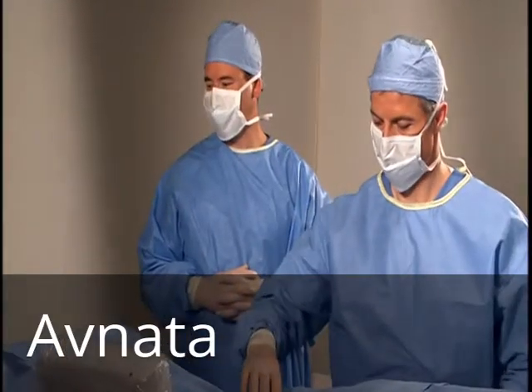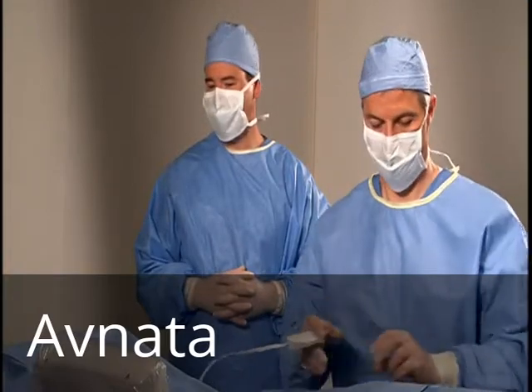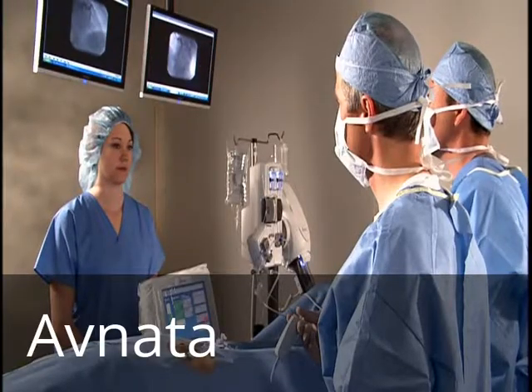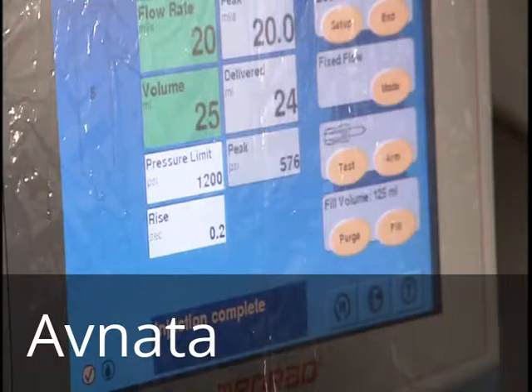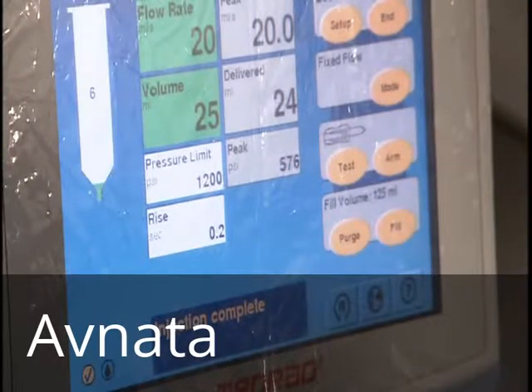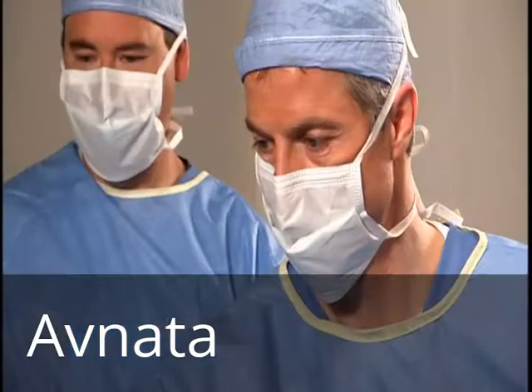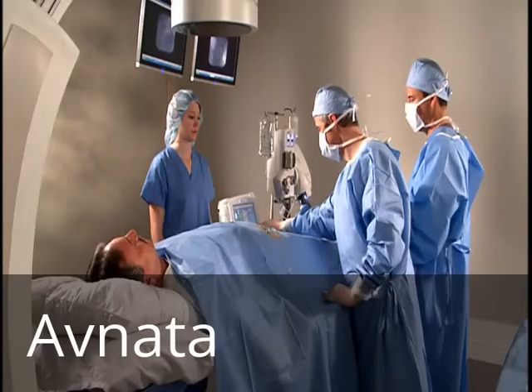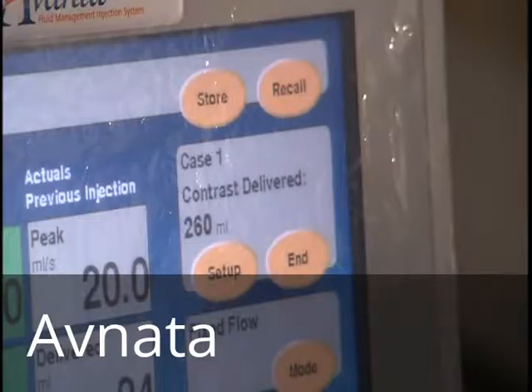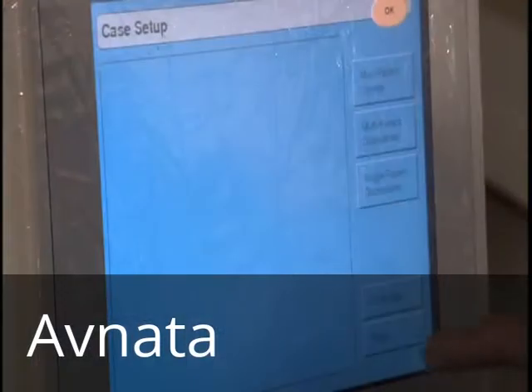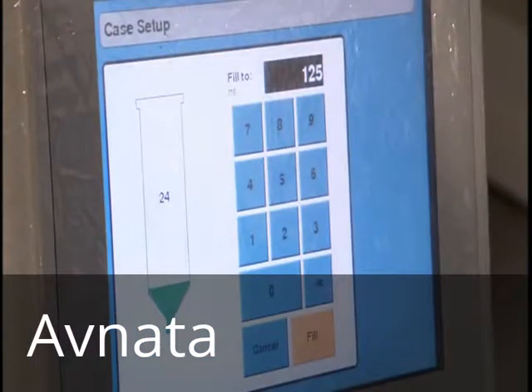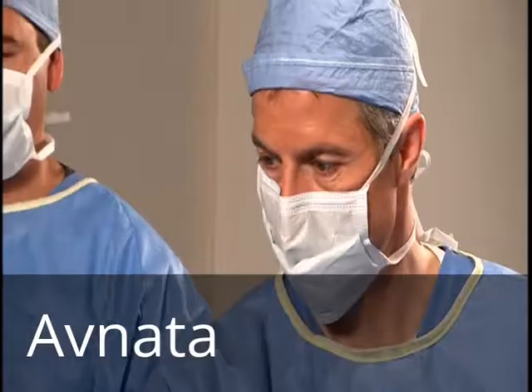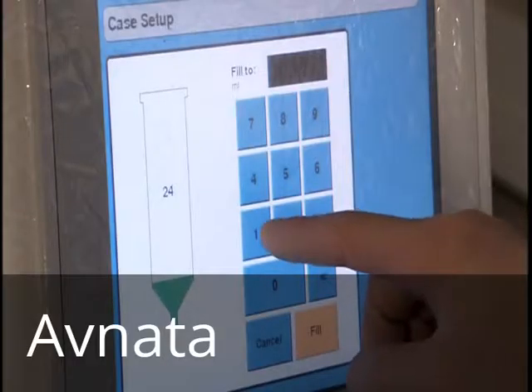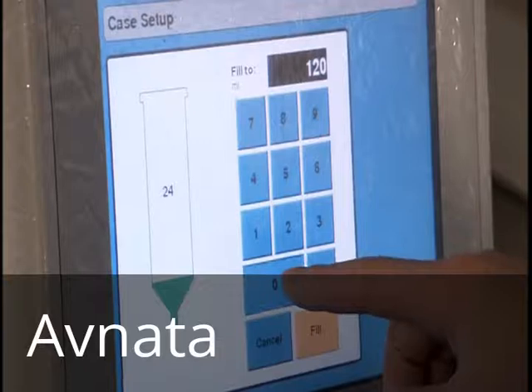When the refill alert is set and the syringe goes below the user-set threshold, an audible alert of 5 beeps will sound, and the syringe will blink 5 times. Manual fill can be initiated when the system is disarmed. Select Setup on the main screen and touch Fill Syringe. The DCU displays a graphical representation of the volume in the syringe. Then enter the desired Fill To volume and touch Fill.